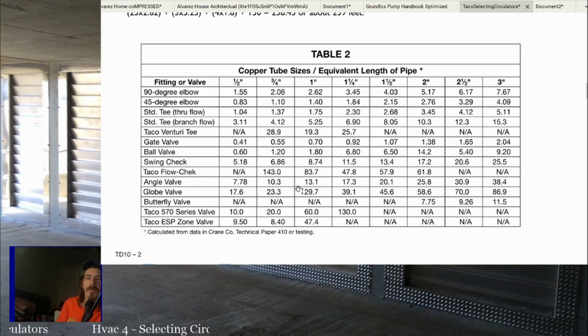Globe valves. If you're familiar with any commercial stuff, your balancing valves, like who makes them? Victaulic. Victaulic makes balancing valves that are built like a globe valve, and those have a very high head loss. The equivalent length of pipe for a 1/2-inch globe valve is 17 feet. For a 3/4 globe valve it's 23 feet. So it adds up. Zone valves can add up. Your 570 series zone valves, a Taco, is 10, 20, 60, 130 feet. The 1.25 inch zone valve equals 130 feet of pipe. So it can be a large head loss. Things like that, you need to pay attention to a lot. Where you have those kinds of items in the circuit, they're very big spots for a lot of head loss. So keep those things in mind.